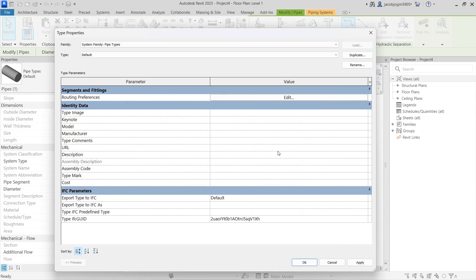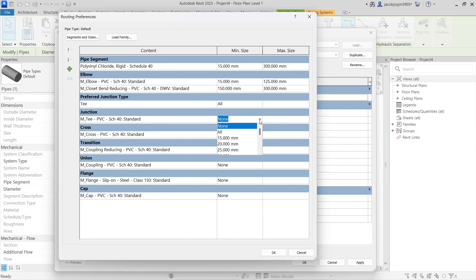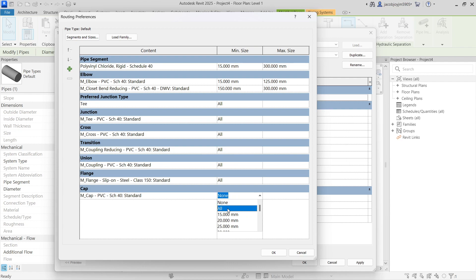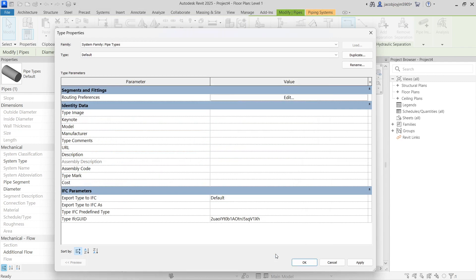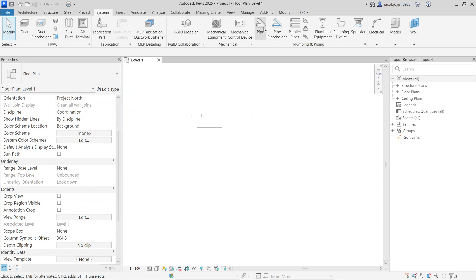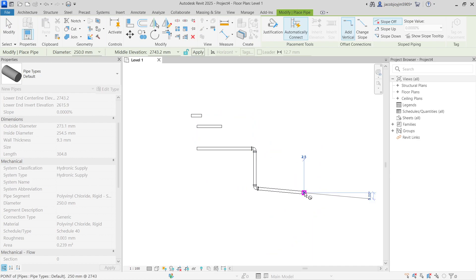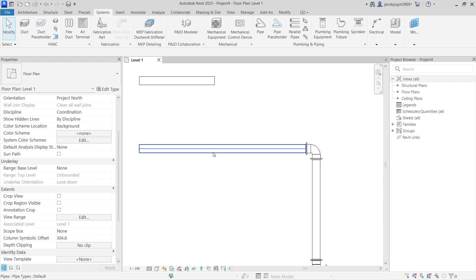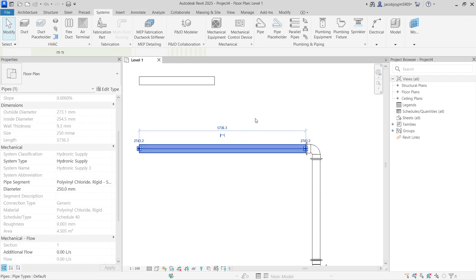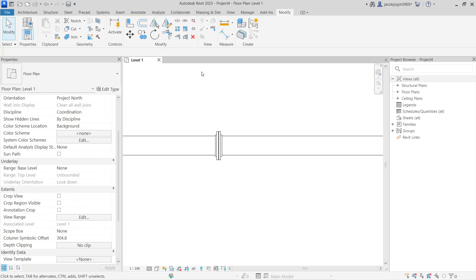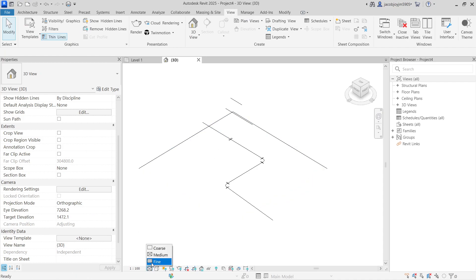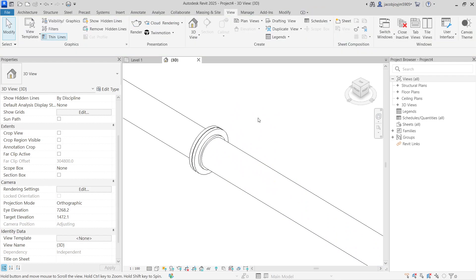For Flange, it's not available in PVC so load from Steel Flanges — any standard will do. Set the sizes for each fitting, then say OK. Now I can draw the pipe. If I go to the Modify tab and use Split Pipe to split this pipe, you can see the flange is generated automatically. This is how you create a pipe type.